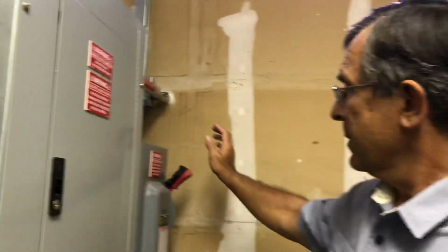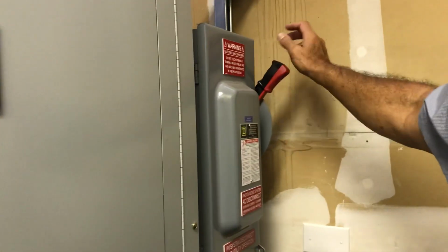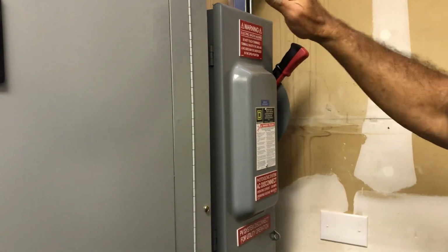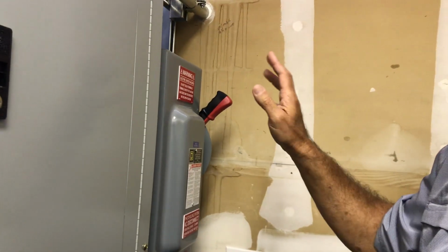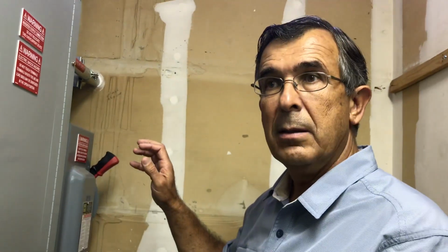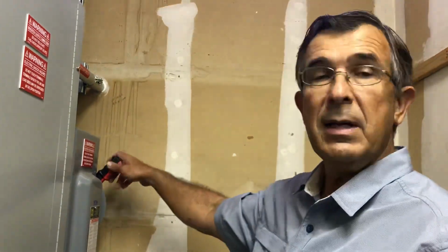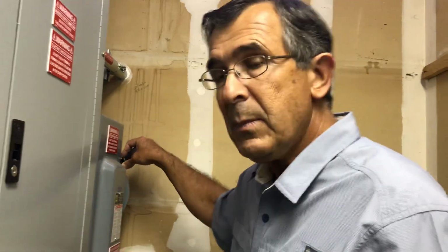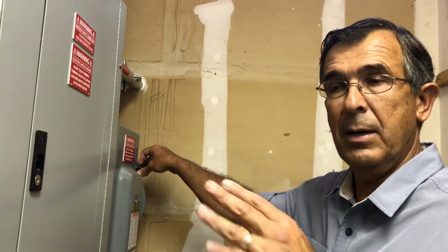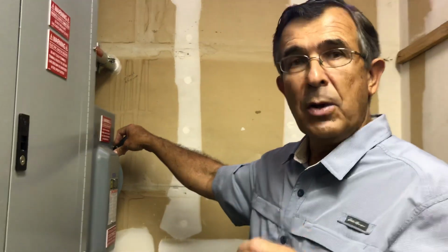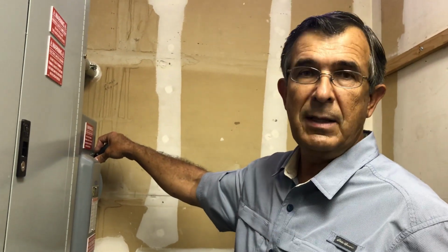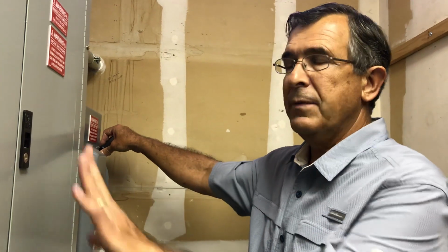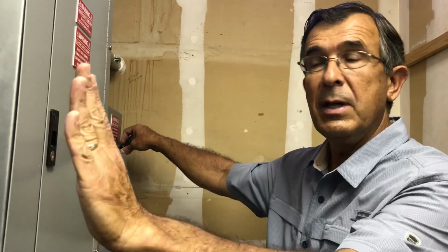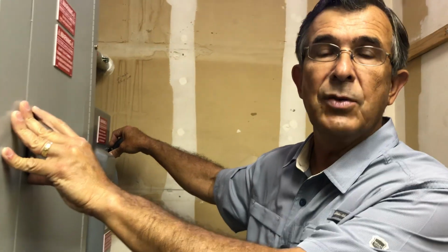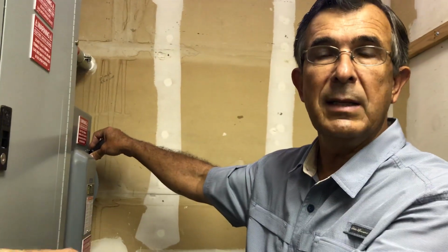The first thing we do is we install a safety disconnect. This allows us and emergency personnel, anyone who wants to service the system, to flip this switch and turn off all power connection between the utility meter and the inverters. By doing this, the inverters will also turn off. And that's something I forgot to mention out there when we were at the carport earlier. The SolarEdge technology we use is also one of the safest in the industry. As soon as you turn off the connection to the utility power, modern inverters are designed to turn off. And that's a safety feature so that no one gets electrocuted.